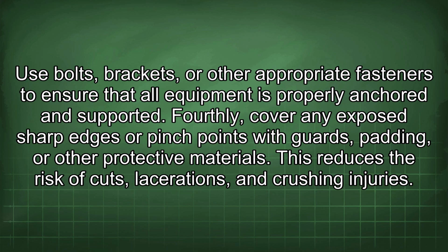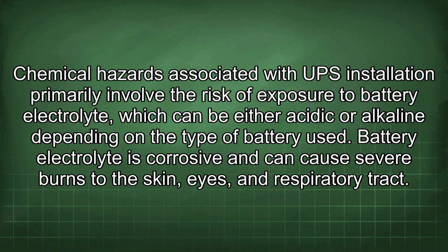Fourthly, cover any exposed sharp edges or pinch points with guards, padding, or other protective materials. This reduces the risk of cuts, lacerations, and crushing injuries. Chemical hazards associated with UPS installation primarily involve the risk of exposure to battery electrolyte, which can be either acidic or alkaline depending on the type of battery used. Battery electrolyte is corrosive and can cause severe burns to the skin, eyes, and respiratory tract.